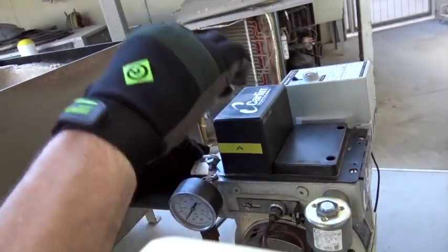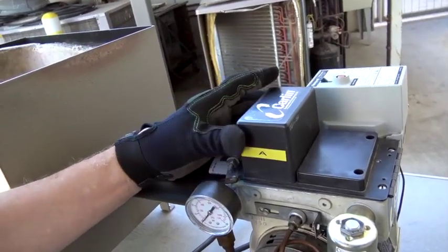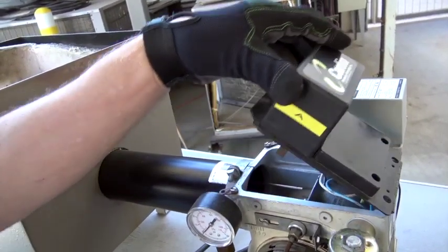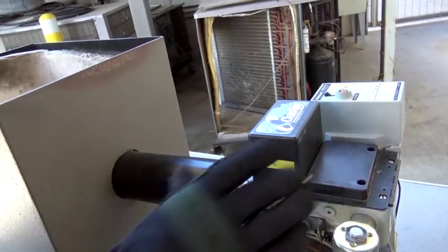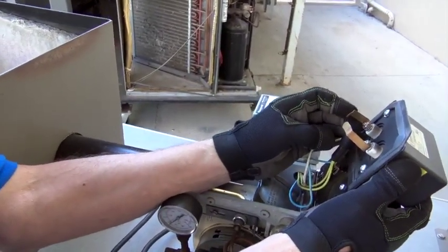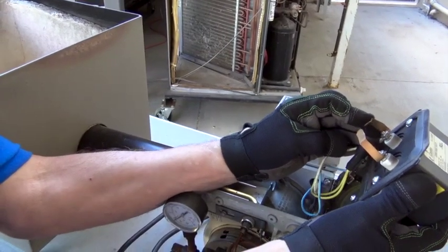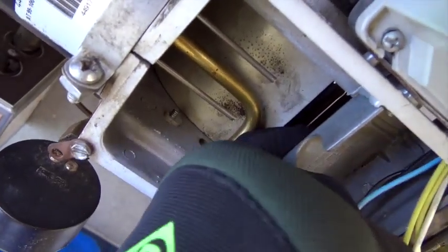And it's got to be tight, real tight, and spring up. If it ain't springing up, you ain't hitting them electrodes, or you're hitting something else. So you got to make sure you hit that thing just right. And these will wear out, and I think the next time we're going to get some new ones here. This is our combustion wheel that's down there.